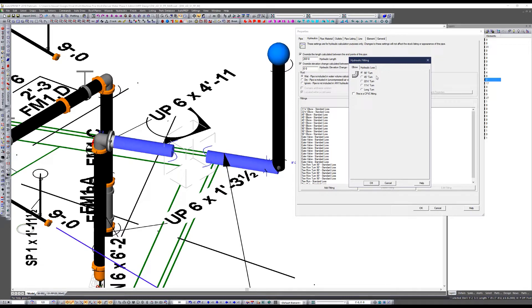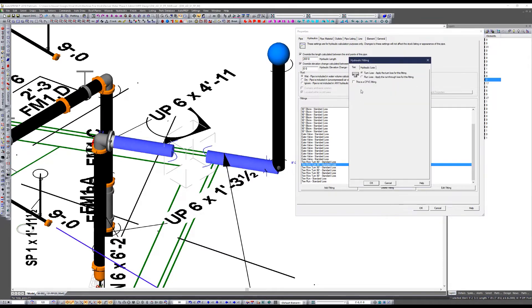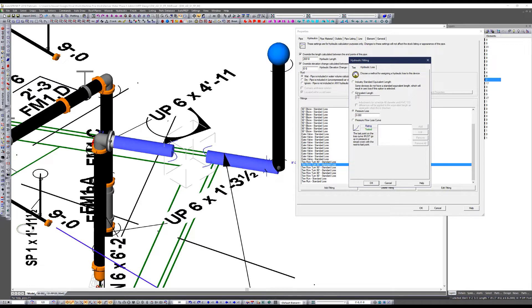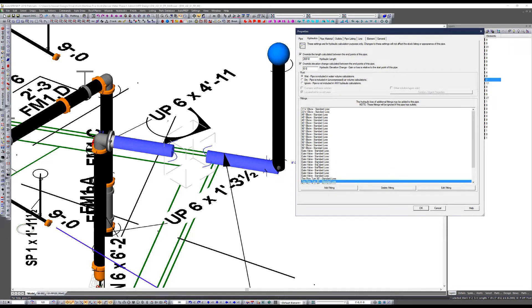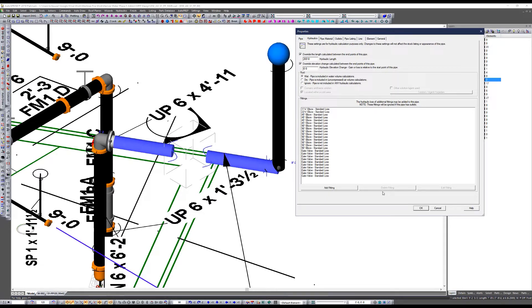After you add fittings, the program asks what type — turn loss, run loss, what type of elbow. You can only select one type at a time, so if I add eight elbows but only want four to be 90s, I should add four at a time — do the 90s first and then the 45s after. I'm telling the program to use the standard losses, which come straight from the NFPA 13 table for these fittings based on pipe diameter. You also have the ability to specify a very specific equivalent length or pressure loss per fitting or valve if you want.